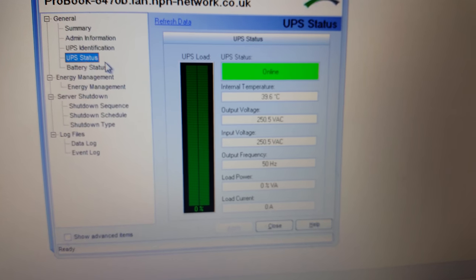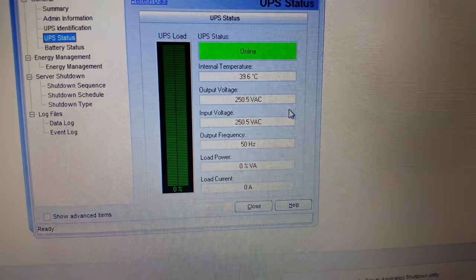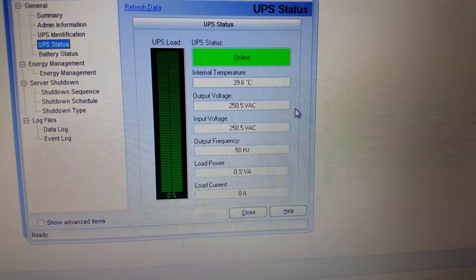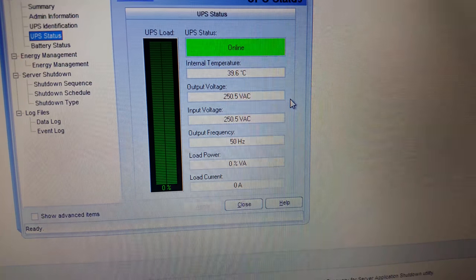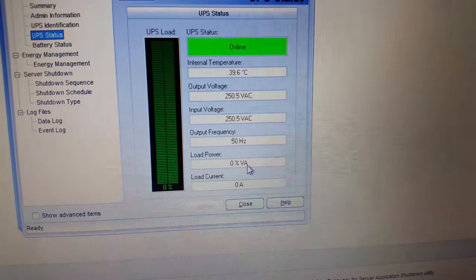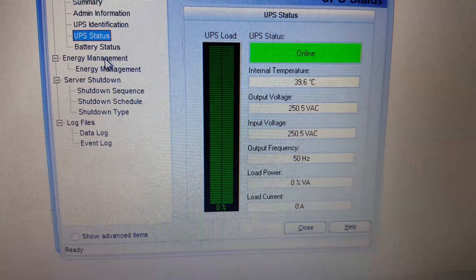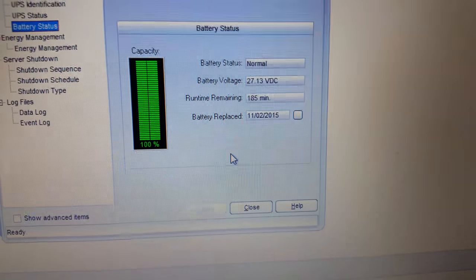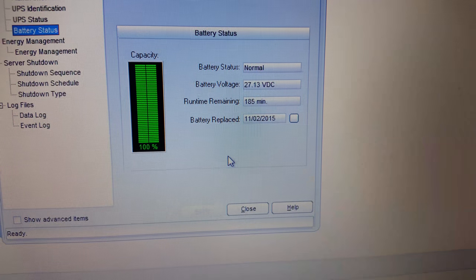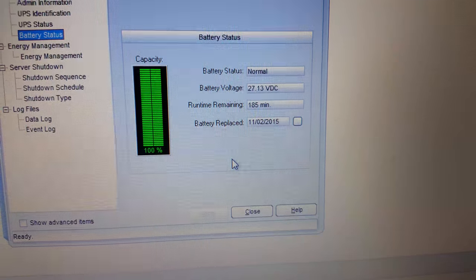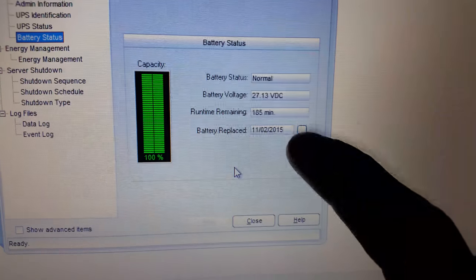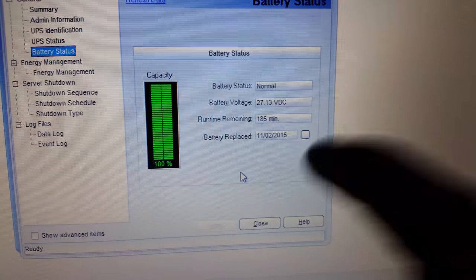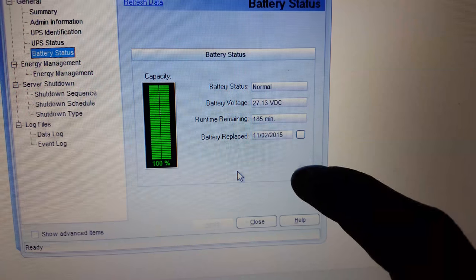If I go to UPS status, it's all online and healthy. Internal temperature 39.6 degrees C, 250 volts AC out, 250 volts AC in, 50 Hertz, zero load on it because there's nothing plugged in obviously. Let's look at battery status and it states the batteries are normal. It's 27.13 volts DC on them and it estimates 185 minutes of runtime remaining. I do remember setting this date when I last changed the batteries, so that's definitely the day they were changed.